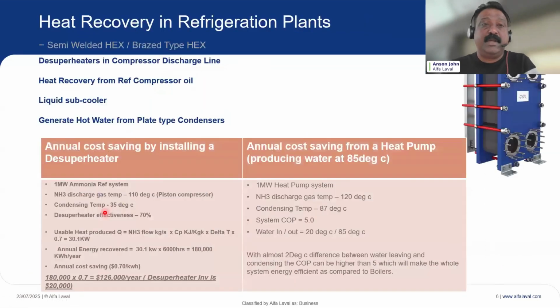Since most of us are working in the food and beverage industry, I understand that most of us will have industrial refrigeration plants, or even commercial refrigeration plants. And there is a lot of heat recovery possible in refrigeration plants. You can add a de-superheater in a compressor discharge line. You can do heat recovery from the hot oil from the compressor. You can add a liquid subcooler, and you can generate hot water from plate type condensers. That's getting pretty common. And if you ask me, in New Zealand this hot water generation from plate type condensers is pretty common these days.